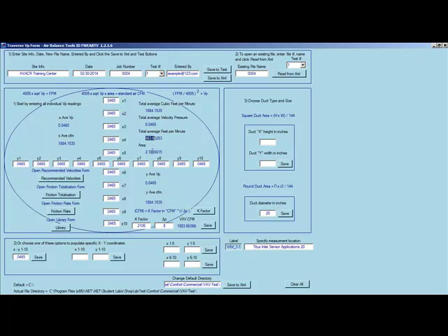This particular duct, as you can see, that 20-inch box has a smaller area. It's got a 0.778 area, so it's actually less than 20 inches. It's quite a bit less, right? Because the area of a 20-inch duct is 2.18. This is why you can't, or in the past you couldn't, use your magnehelic on a VAV box to calibrate or troubleshoot without having to do the equation. This tool does it for you.